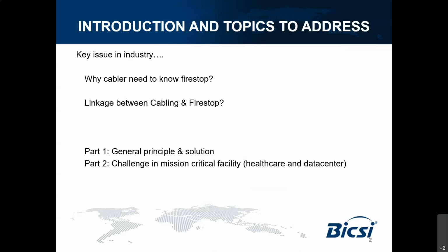Fire stopping is about sealing any surface crossing a barrier - any penetration or opening needs fire stopping. This crosses different trades, not only cabling but also plumbing and other services. Whenever there's an opening in a fire-rated wall, we need to seal it to maintain the integrity of the barrier. Cabling is especially tricky because of the variety of cables - conduit or no conduit, big bundles, single cables - all variations we need to consider in fire stopping design.